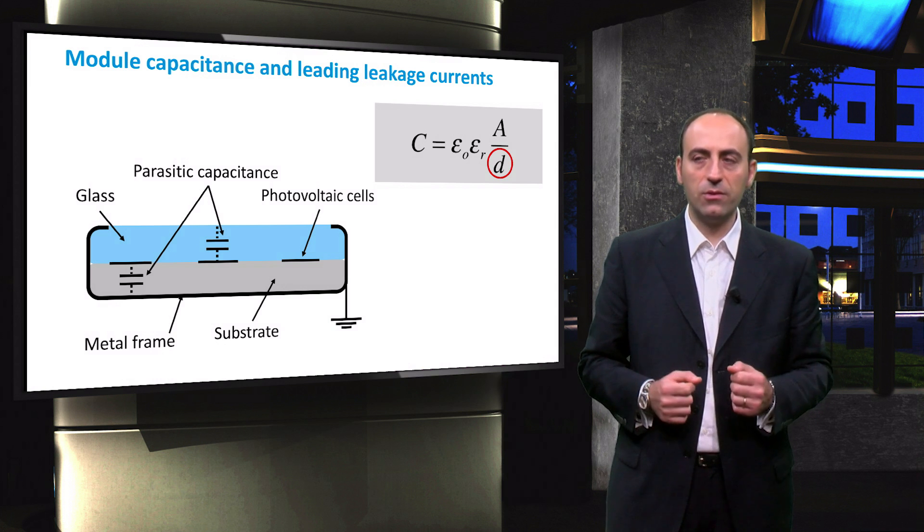The value of the capacitance is also dependent on the atmospheric conditions, mostly dust and humidity. The top of the module, which is covered with glass, is non-conductive when clean and dry. On heavy rain days, this part becomes conductive due to the presence of water and mineral salts accumulated on top of it. The effective area of the capacitor increases significantly, causing the capacitance to increase.